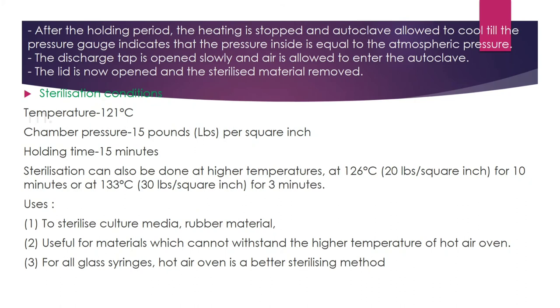After the holding period, heating is stopped and the autoclave is allowed to cool until the pressure gauge indicates pressure equal to atmospheric pressure. The discharge tap is opened slowly, air is allowed to enter, the lid is opened, and the sterilized material is removed. Sterilization conditions: temperature 121°C, chamber pressure 15 psi, holding time 15 minutes.